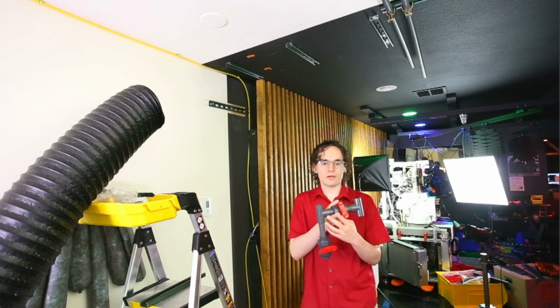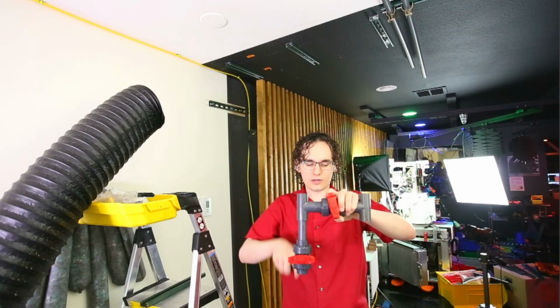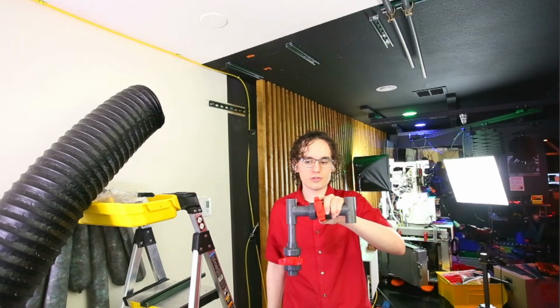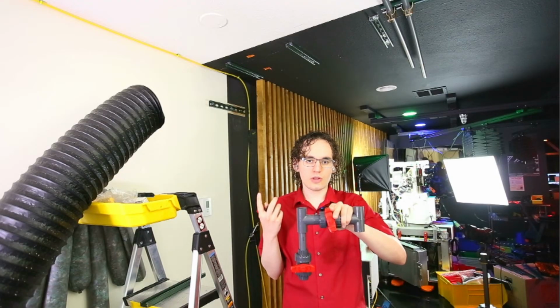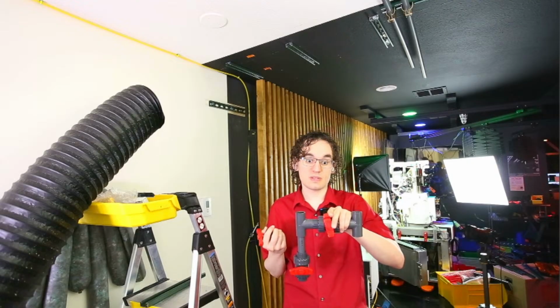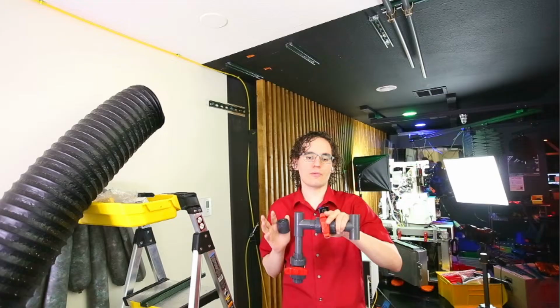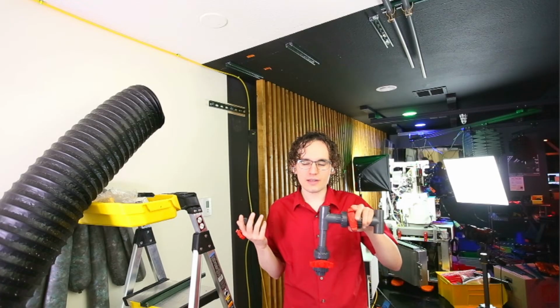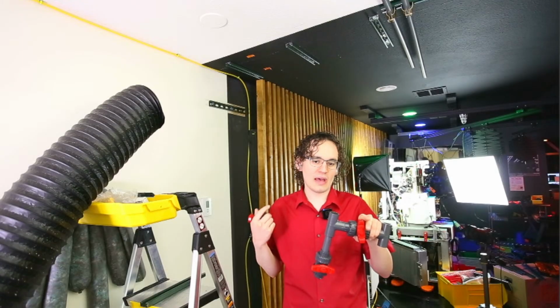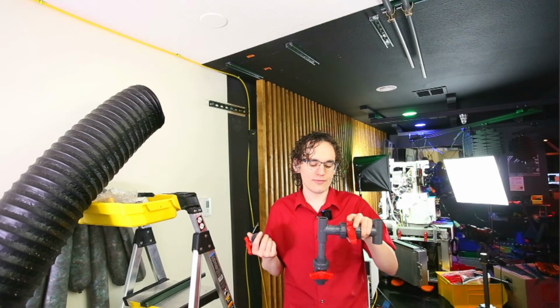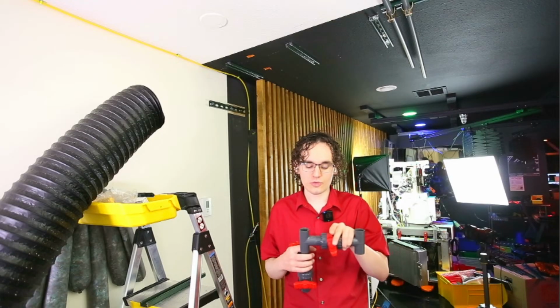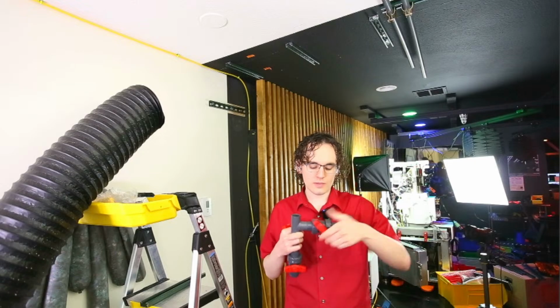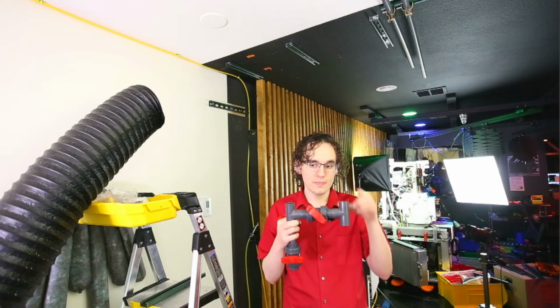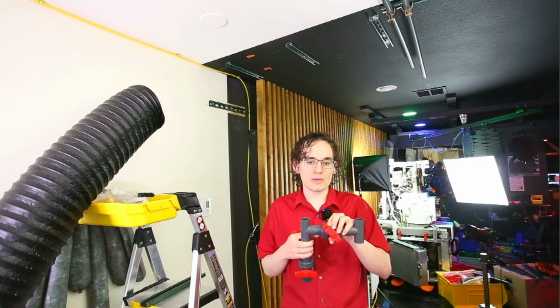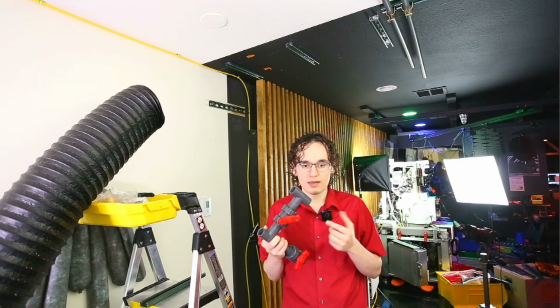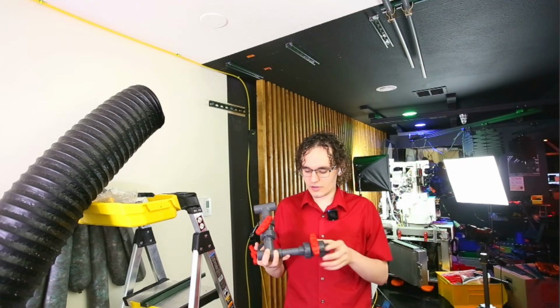So our water is going to come down, go through one side, go through the microscope, come back, go back up, and the return. So why is there this valve in the middle? A lot of the chillers that we're going to be using, specifically the Thermoflex chillers, have an insane flow rate, like 40 something liters per minute. And this microscope needs like 0.5 liters per minute. So we're going to take advantage of that high flow rate to maintain really good temperature stability through the cooling loop. But most of the flow is actually going to be bypassed by opening this valve partway. So most of our flow is going to be bypassed, and just some of it's going to go to the microscope. But because we have a really high mass flow rate through the tubes, we're going to maintain really good temperature stability.